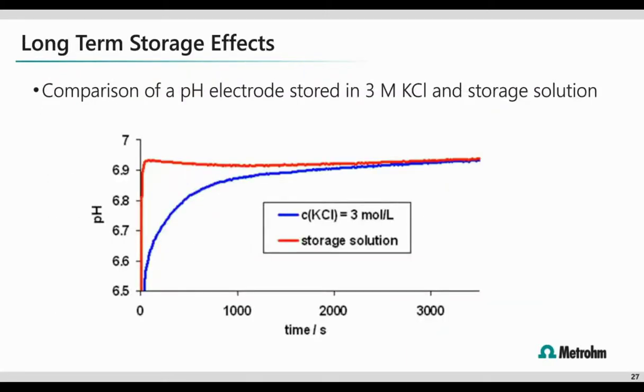We often get the question, why can't I just store it in my KCl electrolyte solution? So the graph on your screen now will really help you understand and explain why we don't recommend this. If you focus on the blue line, this represents a pH measurement taken using an electrode that was stored in KCl fill solution. What we see is that the potassium ions have taken up residence in the electrode membrane, and it took up to the 1,000 second mark. So we're looking at just over 15 minutes here for those K+ ions to leave the membrane and allow us to get to an equilibrated pH measurement.